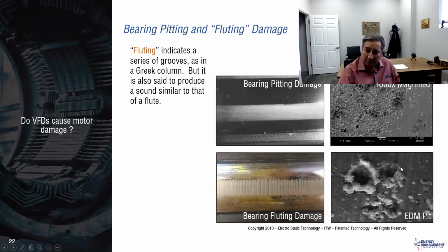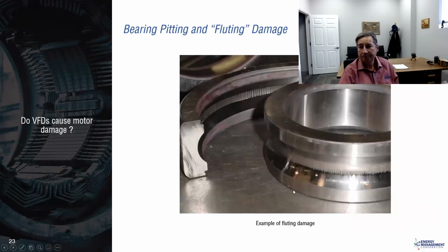So you can see here under a microscope these very small pits, like electrostatic discharge, or like a machine that's actually cutting. It's little pits that it's building up, and then you can see the magnification until it ends up. If there's a bearing problem that we catch, we typically use SPM instruments for our vibration analysis, which use the shock pulse method, which allows us to detect some of these failures a little bit earlier than a typical accelerometer. But this is where it ends up, and you can hear the audible noise for sure at this point. And of course, it can be both in the inner race and the outer race.